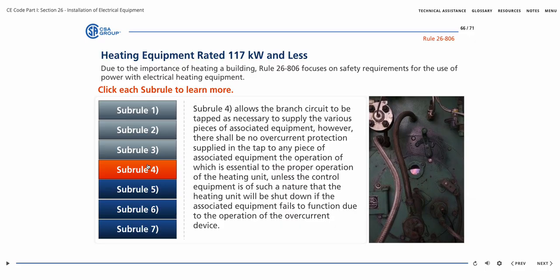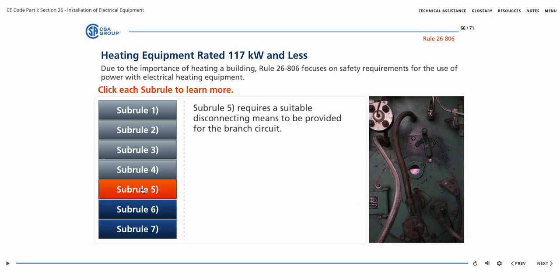However, there shall be no overcurrent protection supplied in the tap to any piece of associated equipment the operation of which is essential to the proper operation of the heating unit, unless the control equipment is of such a nature that the heating unit will be shut down if the associated equipment fails to function due to the operation of the overcurrent device. Sub-Rule 5 requires a suitable disconnecting means to be provided for the branch circuit.